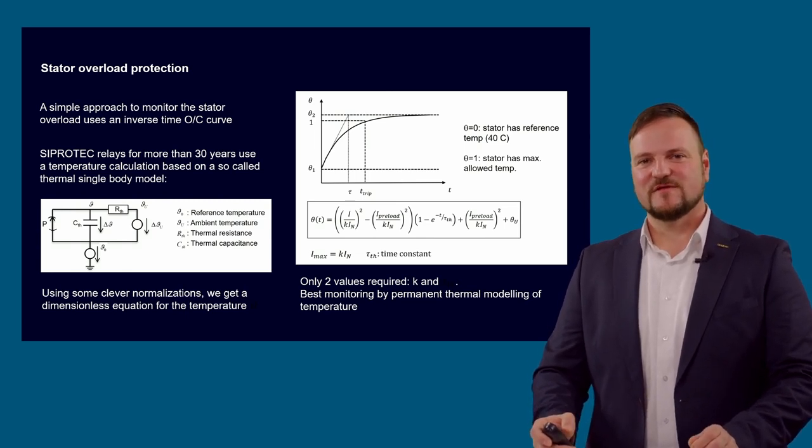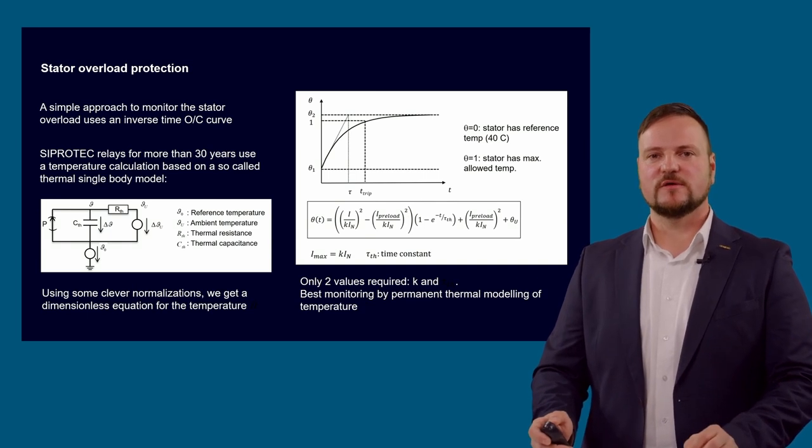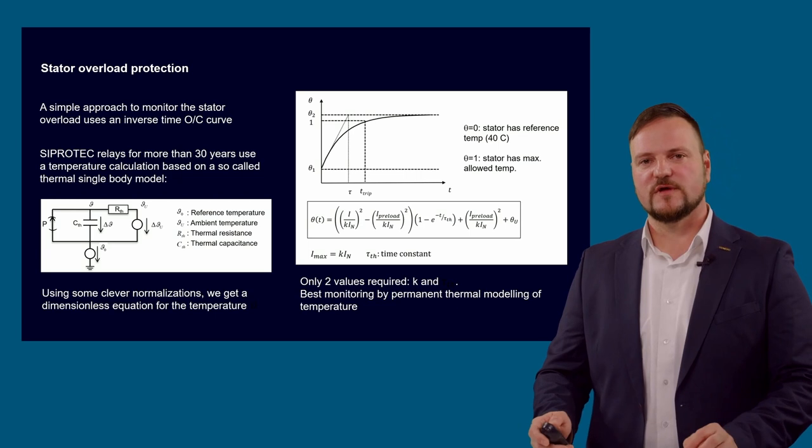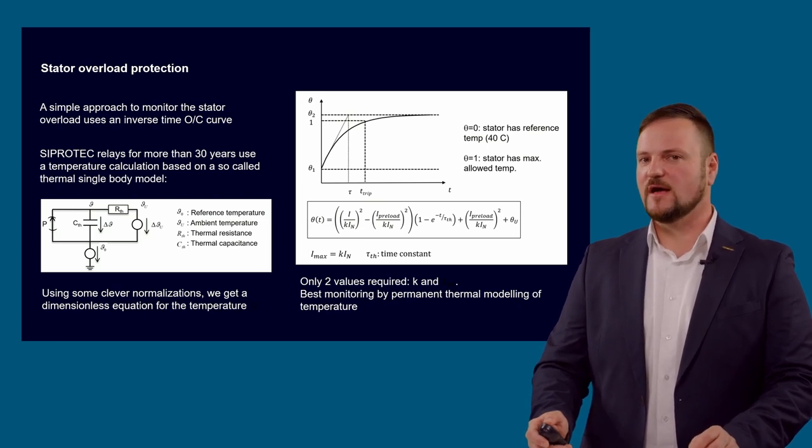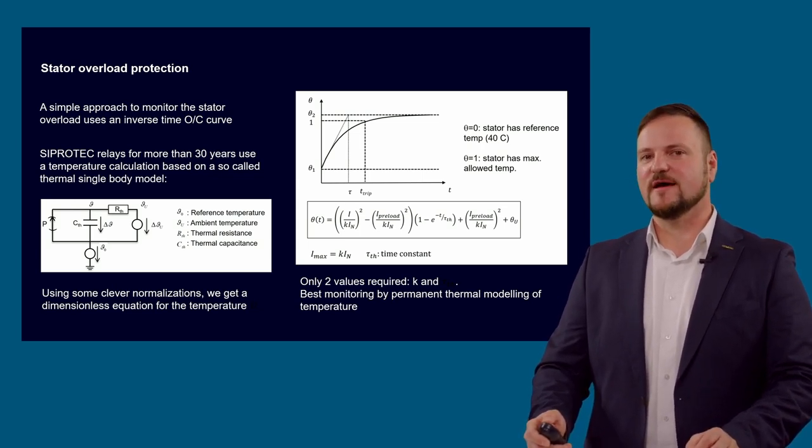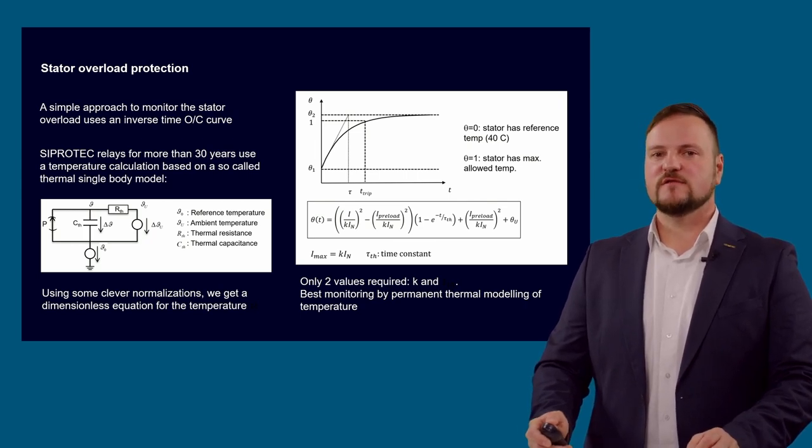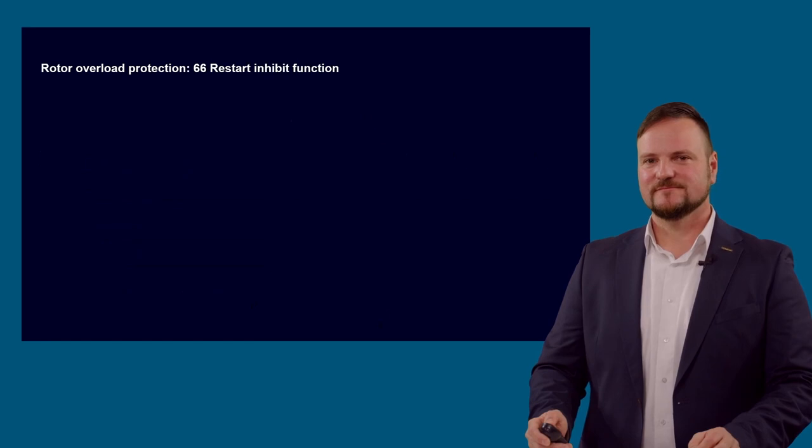The first parameter, this is the so-called k-factor, where k times the nominal current is the maximum permanently permissible current of the machine. This factor normally is around 1.1 or 1.2, that means 110 or 120 percent of the nominal current. The second parameter is the thermal time constant tau, which describes how fast the motor heats up to the new end temperature. Typical values here are between 10 and 30 minutes for a motor. For a permanently fluctuating current, the model increases in a way that the temperature follows accordingly. This model guarantees a permanent supervision of the stator temperature.